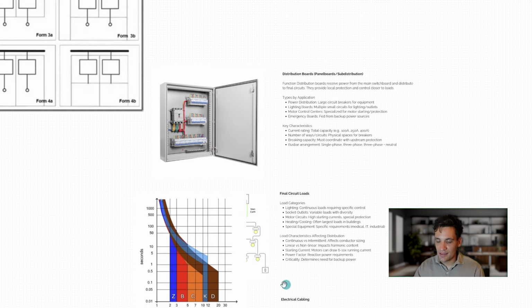We've also got, as we've spoken about on the fundamental sections, loads can have different characteristics. You can have a continuous load, or you can have intermittent loads that have a demand factor applied to them. Again, a toaster is a discontinuous load. You don't always have your toaster operating in your house, but you might have a security system that's always on. So they'll have different demand factors. We can have linear versus non-linear loads. Again, linear loads are like a heater. A non-linear load has something like a rectifier or power electronics that cause disturbance to the power quality.